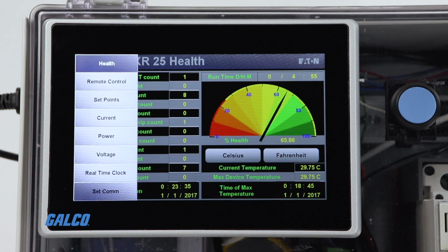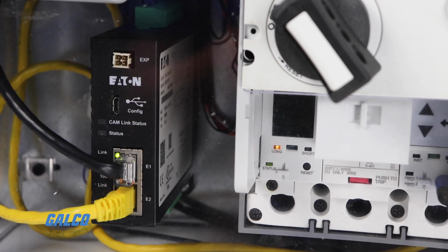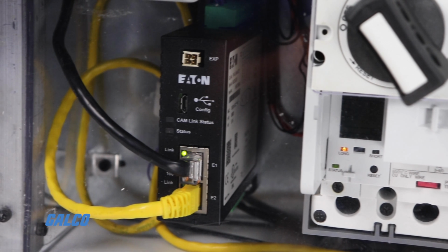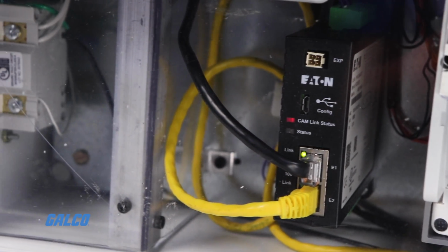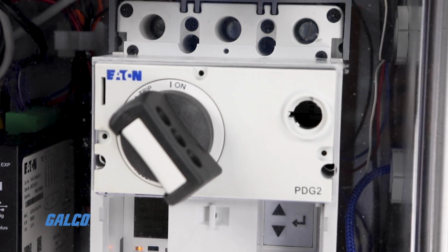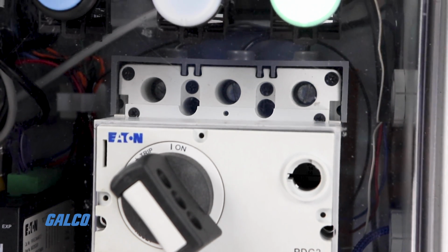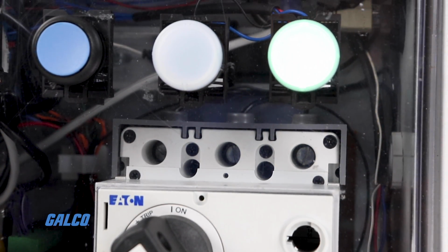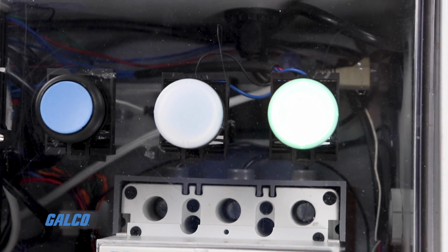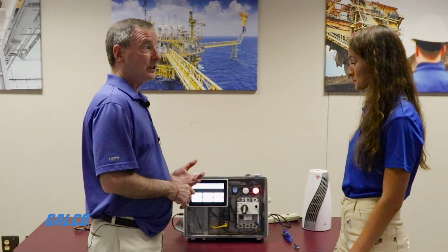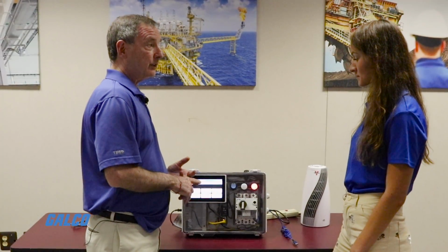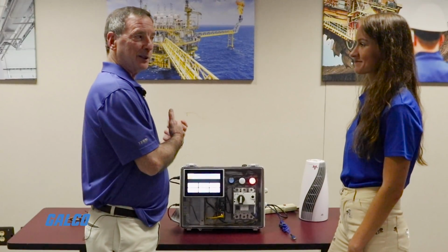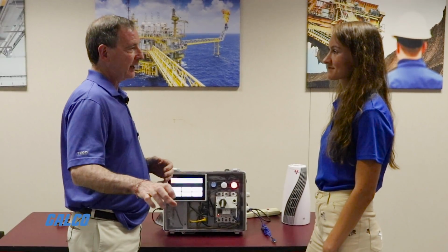And this is just showing a standard, anybody's PLC and HMI talking to a breaker, and you can talk to multiple breakers. So I could have my whole plant. As a matter of fact, Eaton, at two of its plants, we are monitoring every energy use using this technology, every breaker, every load, every cell. We can tell what the energy cost is, when it tripped, why it tripped, what was the current, and we can do that all remotely. So the people in Eaton, in Cleveland, can monitor that plant all the way down to the plant level.